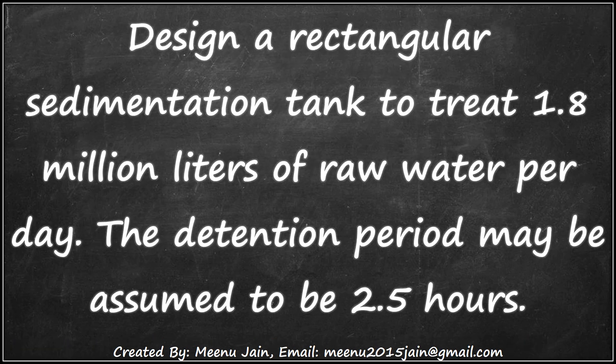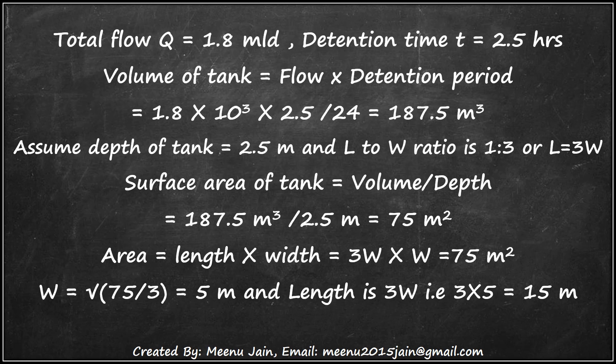Example: Design a rectangular sedimentation tank to treat 1.8 million liters of raw water per day. The detention period may be assumed to be 2.5 hours. If total flow is 1.8 million liters per day and detention time T is 2.5 hours, then volume of tank will be flow multiplied by detention period.